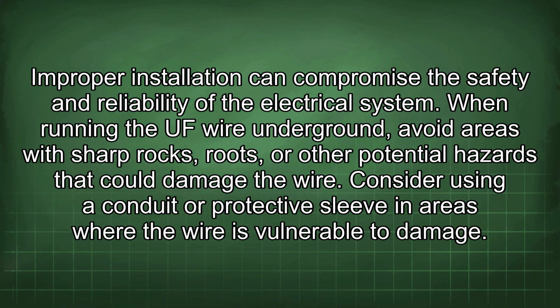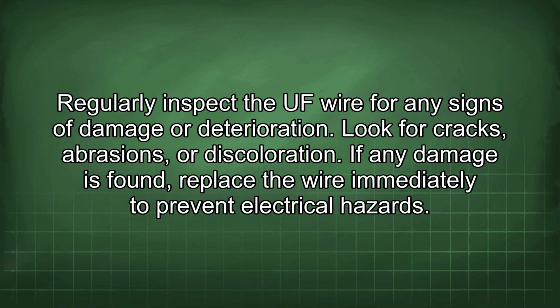When running the UF wire underground, avoid areas with sharp rocks, roots, or other potential hazards that could damage the wire. Consider using a conduit or protective sleeve in areas where the wire is vulnerable to damage. Regularly inspect the UF wire for any signs of damage or deterioration. Look for cracks, abrasions, or discoloration. If any damage is found, replace the wire immediately to prevent electrical hazards.